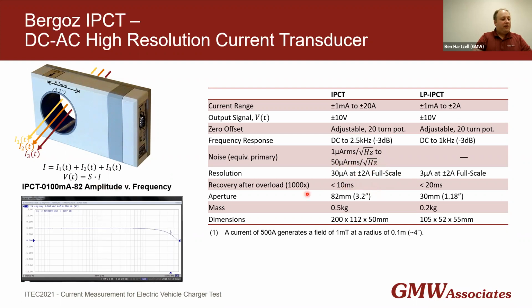And another feature here that may be useful is the recovery after overload. So with 1,000 times overload current, it will recover very quickly, less than 10 milliseconds. We also have a newer version here, the LP-IPCT, which is smaller, more compact, and lighter, but the aperture is also smaller. So depending on where you tend to use it, it may be a little bit more difficult to get these large cable bundles through. But the main advantage here is the higher resolution.